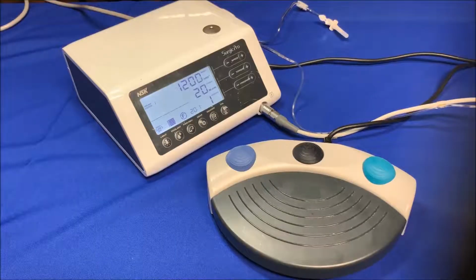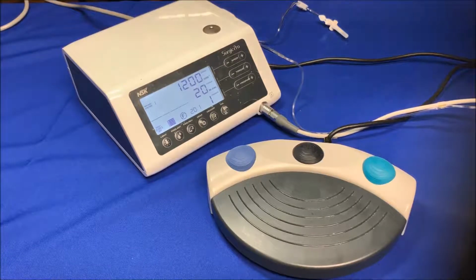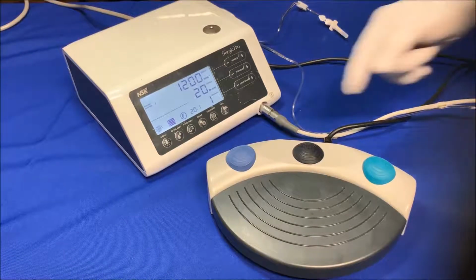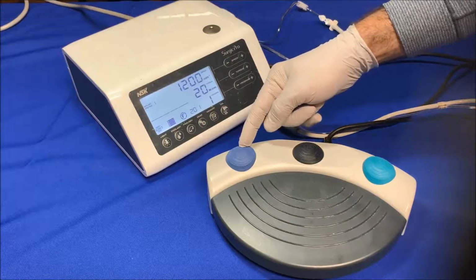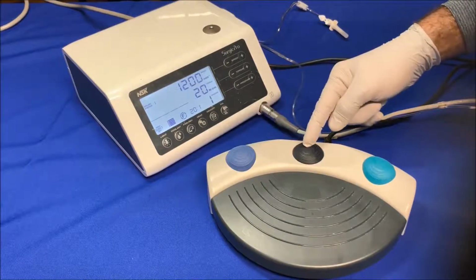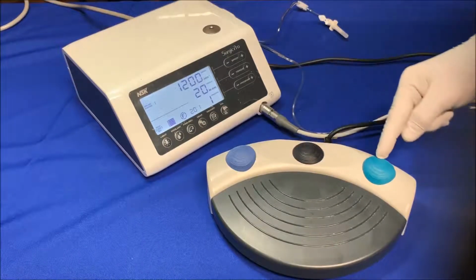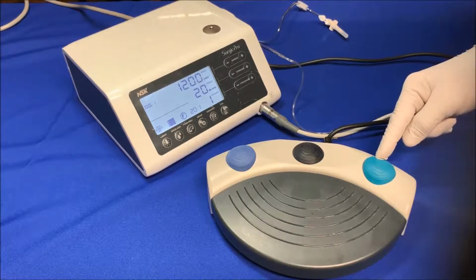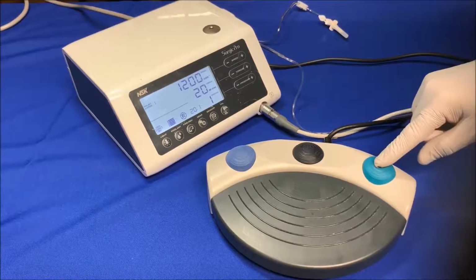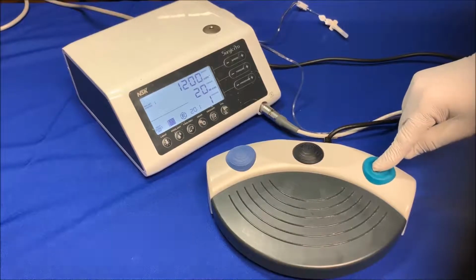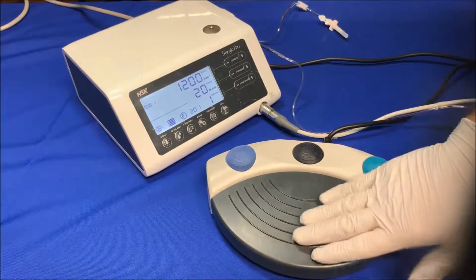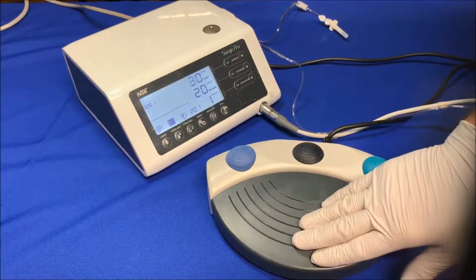Foot control. You can choose the programs, irrigation, and forward or reverse on the foot control during the operation to avoid touching the front panel by hand. Like I said, the blue button adjusts the coolant flow, the black one runs through 8 preset programs, and the green button switches between forward or reverse. The reverse gives a beep sound, by the way. Speed control pedal to run the motor.